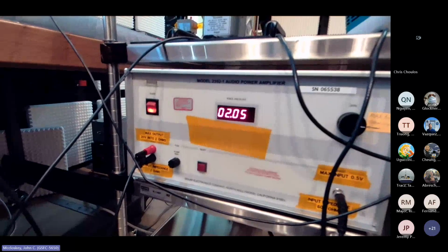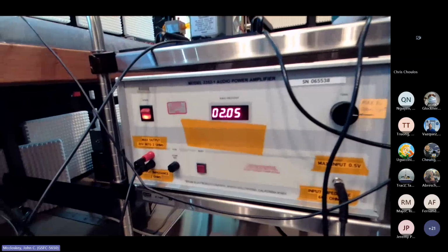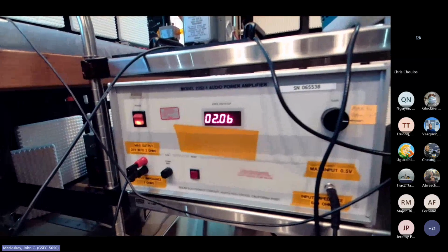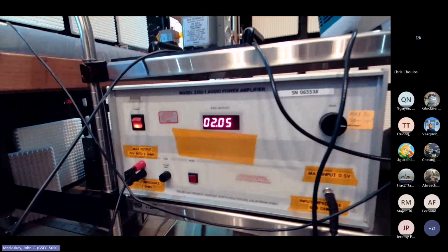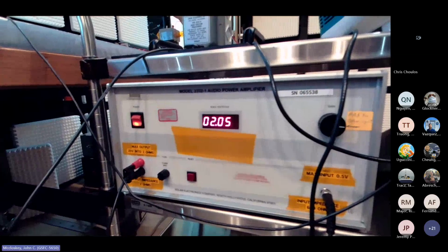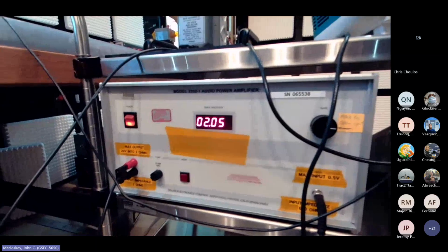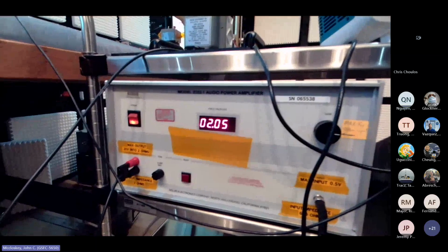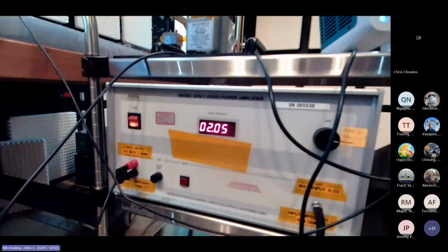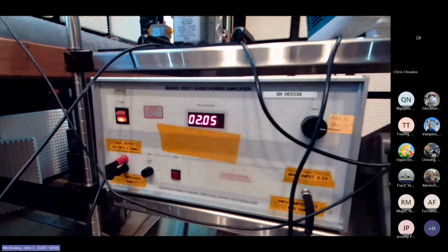That's right in line with what we would expect, just from V equals IR. Well, this is into the UUT, not into the calibration resistance, so this may be apples and oranges. But just at the low frequency end, things are a little bit better behaved. At 30 hertz, V equals IR more accurately than it does at 150 kilohertz.